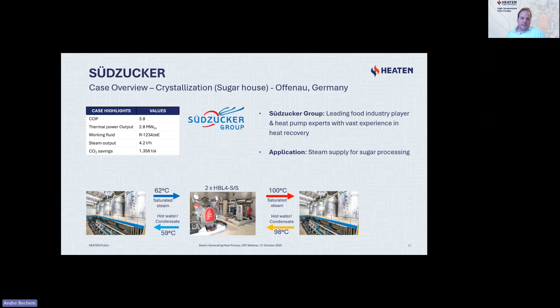The second application at Südzucker, part of the evaporation station, uses a higher heat source and a higher heat sink temperature. In the future, there's also the option to combine these two applications into one, doing the temperature lift we're now doing with two stages, from 60 to 100 and 100 to 130, in a single stage from 60 to 130. Then we would only need one stage instead of multiple, making it more flexible in terms of integration.